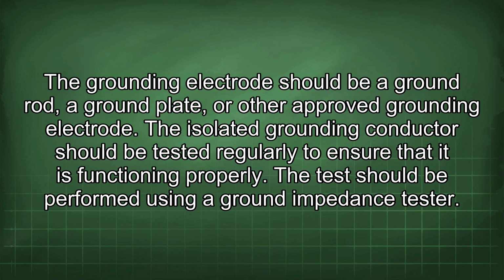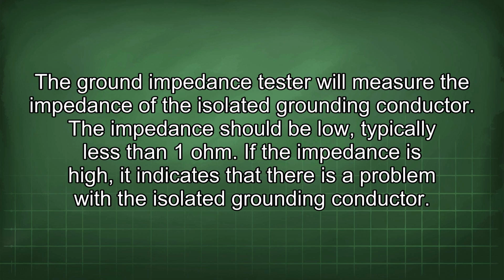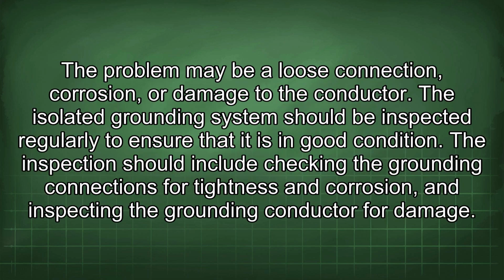The isolated grounding conductor should be tested regularly to ensure that it is functioning properly. The test should be performed using a ground impedance tester. The ground impedance tester will measure the impedance of the isolated grounding conductor. The impedance should be low, typically less than 1 ohm. If the impedance is high, it indicates that there is a problem with the isolated grounding conductor. The problem may be a loose connection, corrosion, or damage to the conductor.